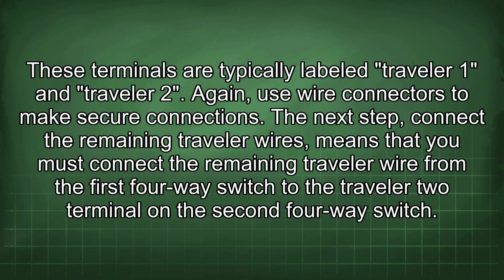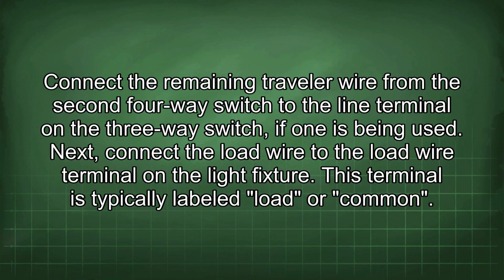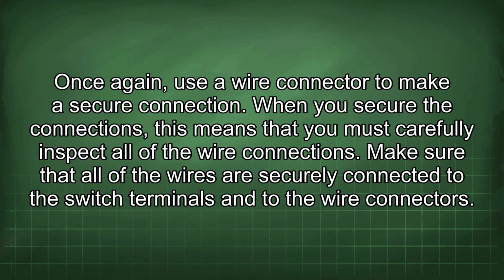The next step, connect the remaining traveler wires, means that you must connect the remaining traveler wire from the first 4-way switch to the traveler 2 terminal on the second 4-way switch. Connect the remaining traveler wire from the second 4-way switch to the line terminal on the 3-way switch, if one is being used. Next, connect the load wire to the load wire terminal on the light fixture. This terminal is typically labeled load or common. Once again, use a wire connector to make a secure connection.